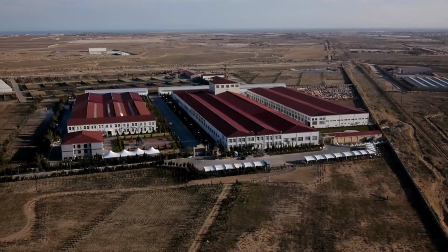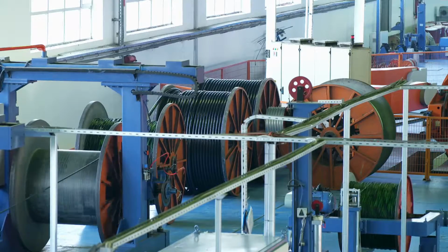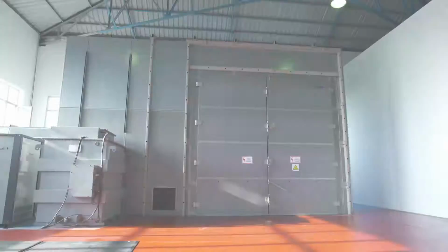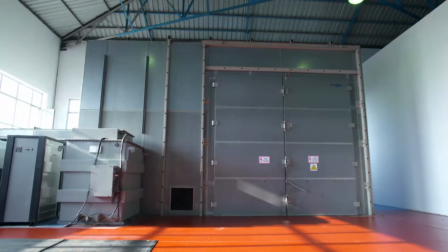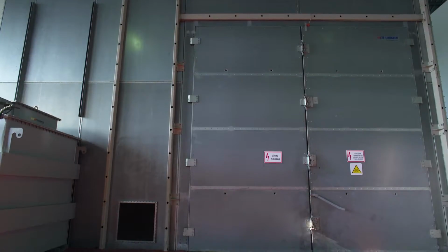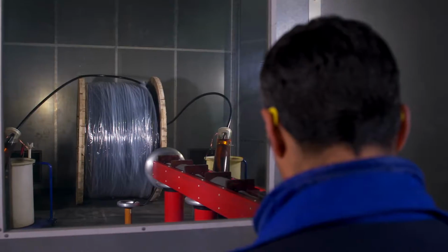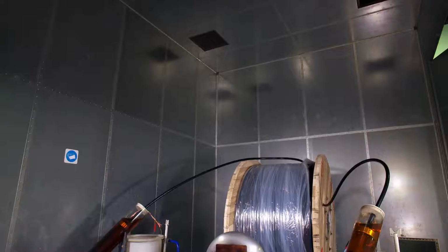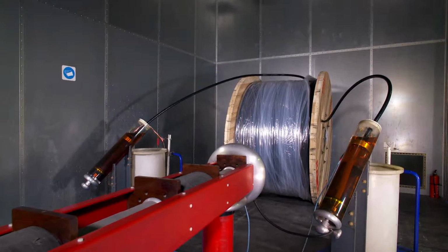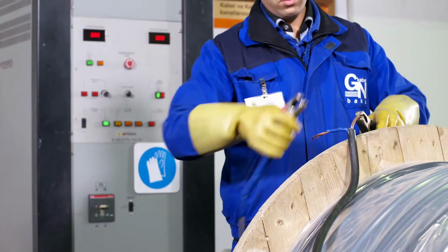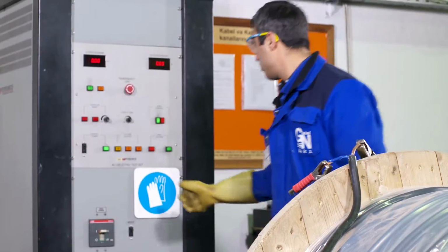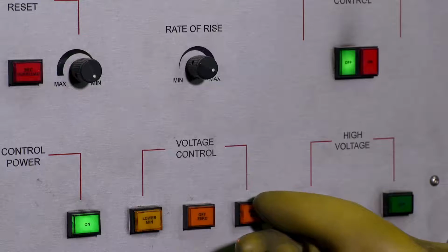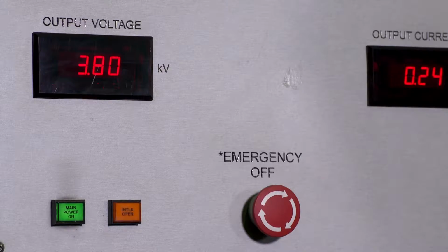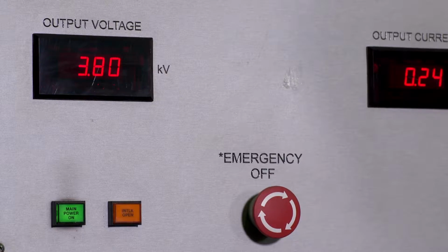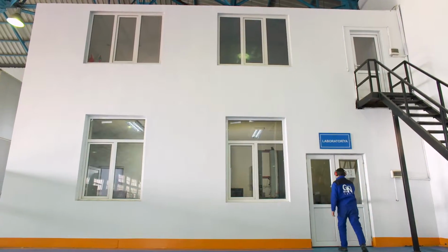Before delivery to the customer, all cables undergo voltage, partial discharge and conductor resistance tests as routine according to regulations or standards. The operator tests the cable at high voltage using termination oil on cable ends. All electrical properties of the cable are measured and defects identified by means of electronic equipment. In addition, cables are checked and tested at every manufacturing process step according to standards and quality plans at the internal laboratory.